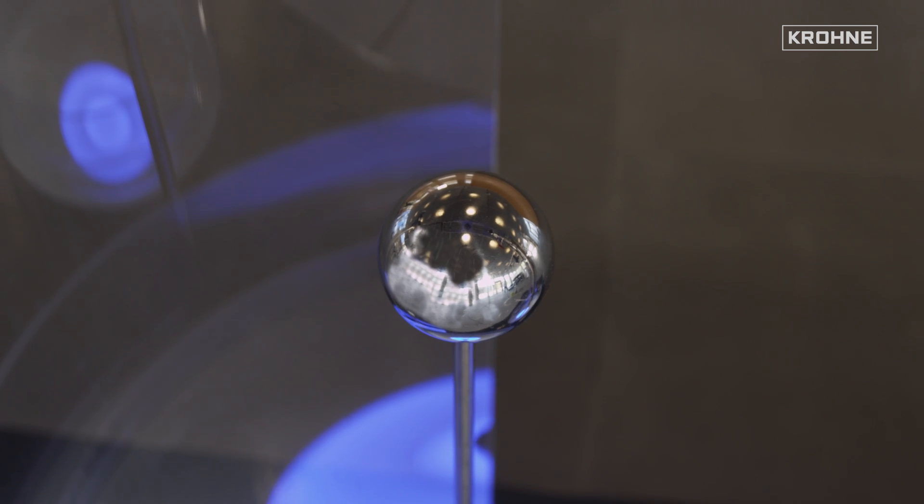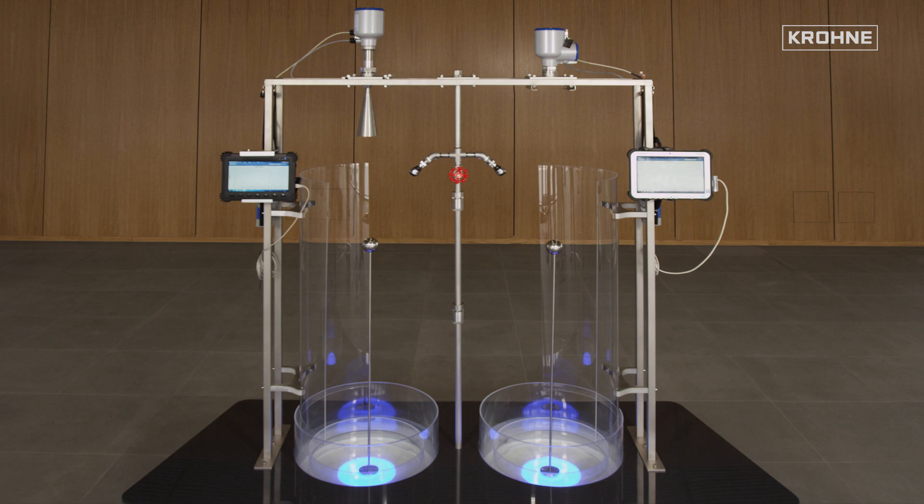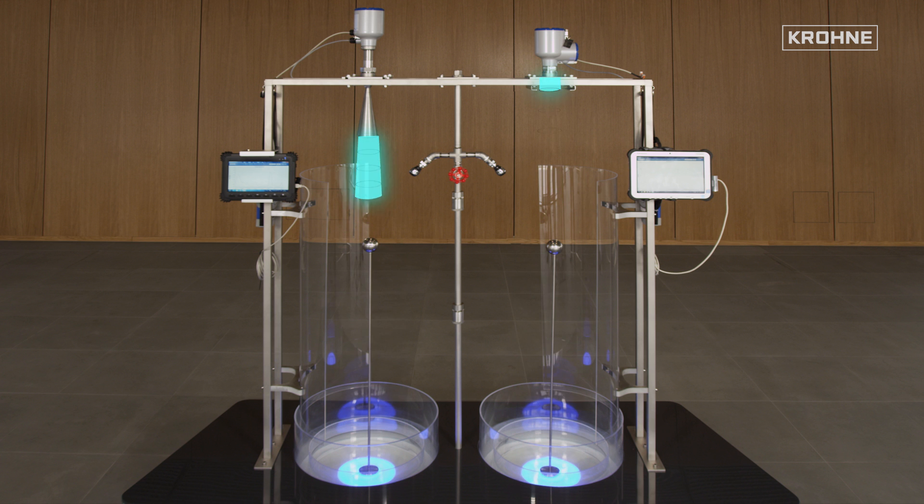A metallic sphere represents a conceivably weak reflector, since only a small part of the radiated signal is reflected back in the direction of the antenna. Thus a sphere can be used to simulate reflections on products with low dielectric constant, the so-called DK value.